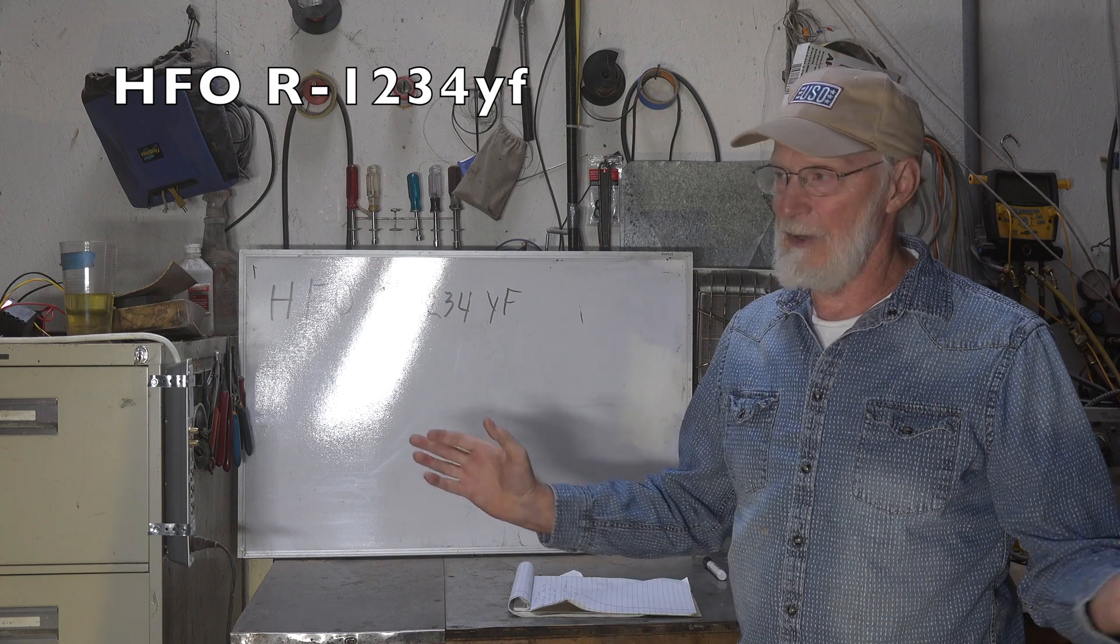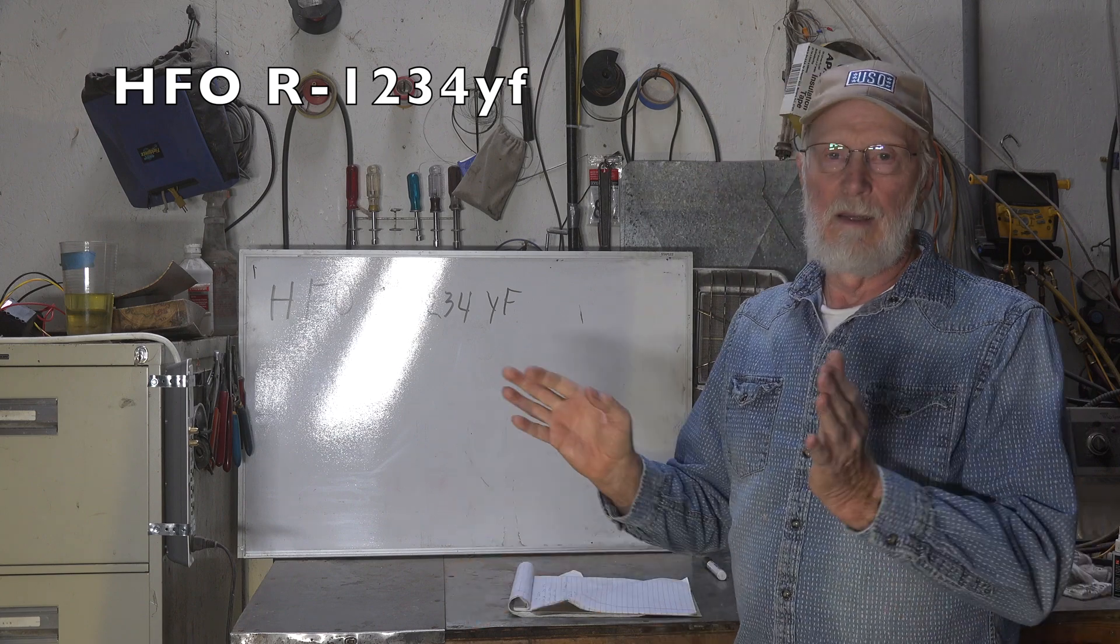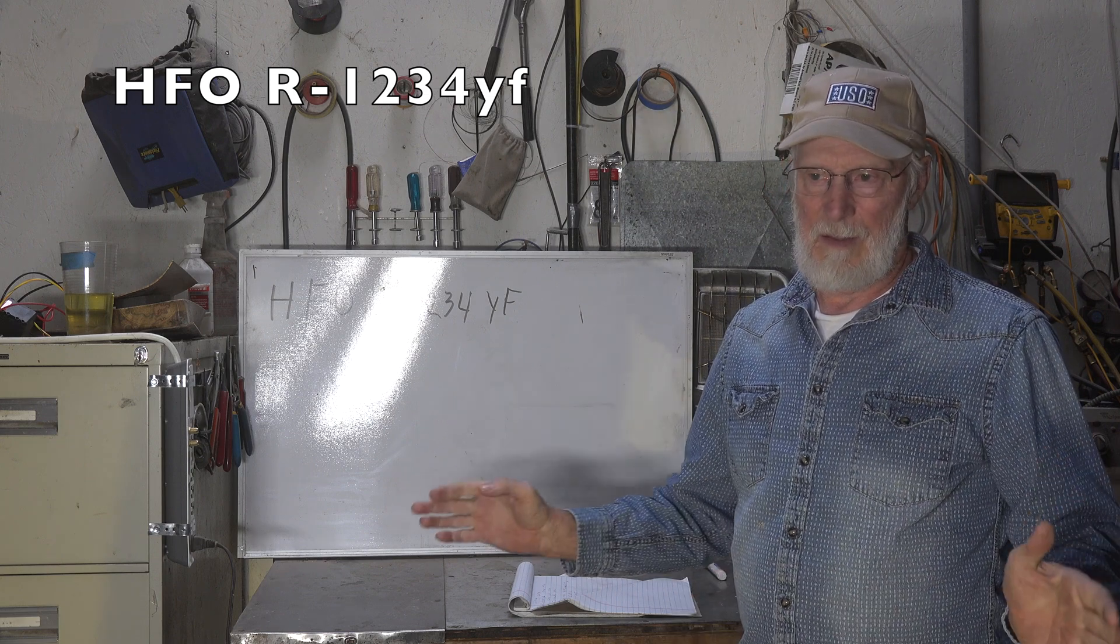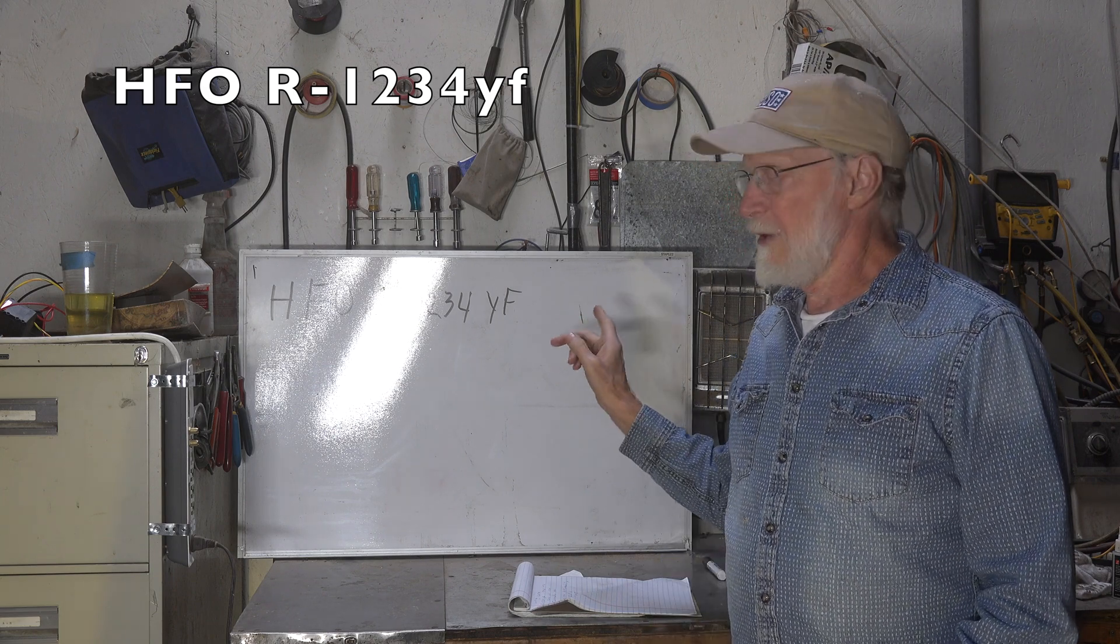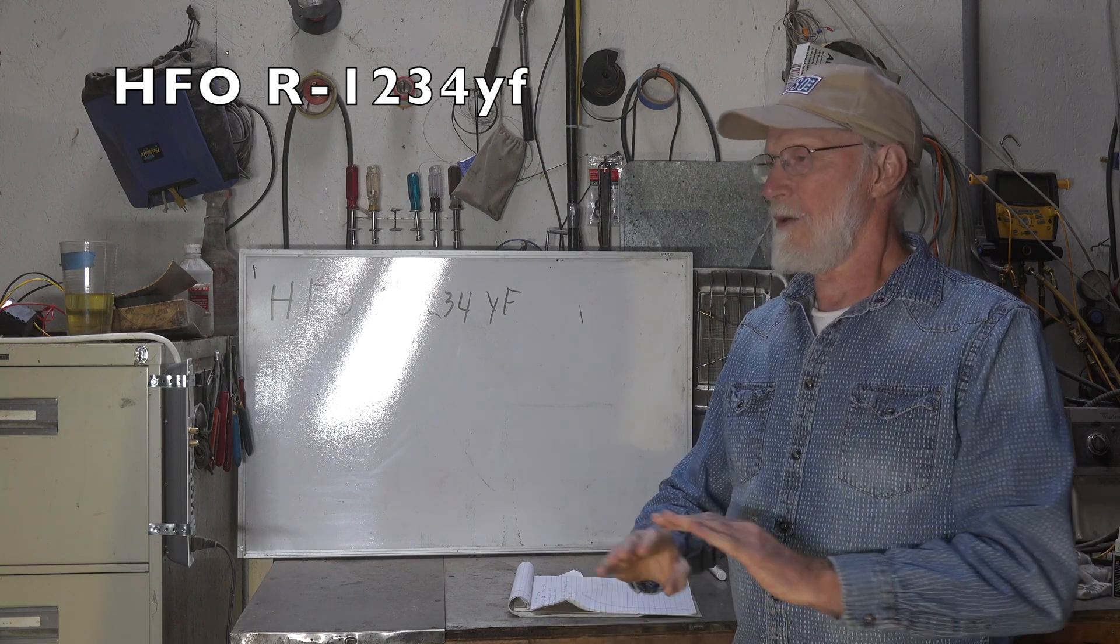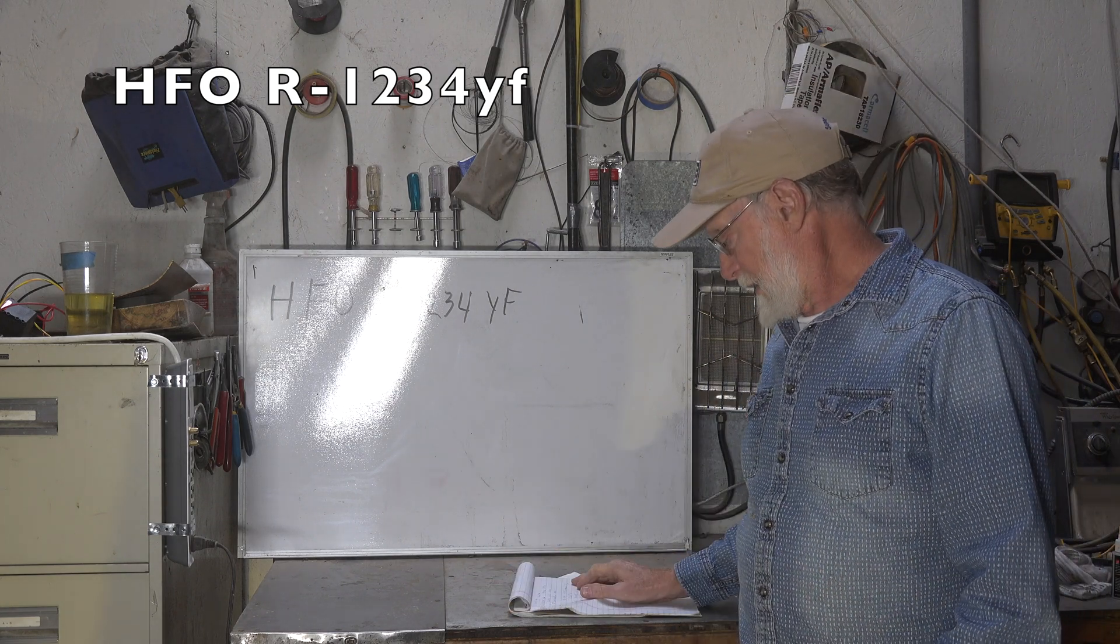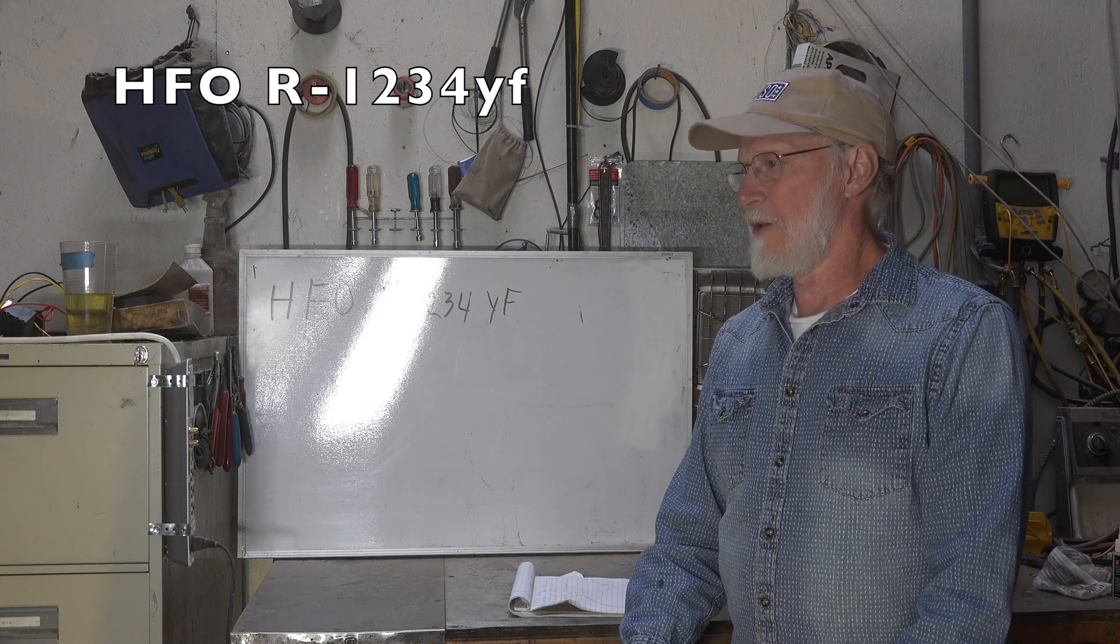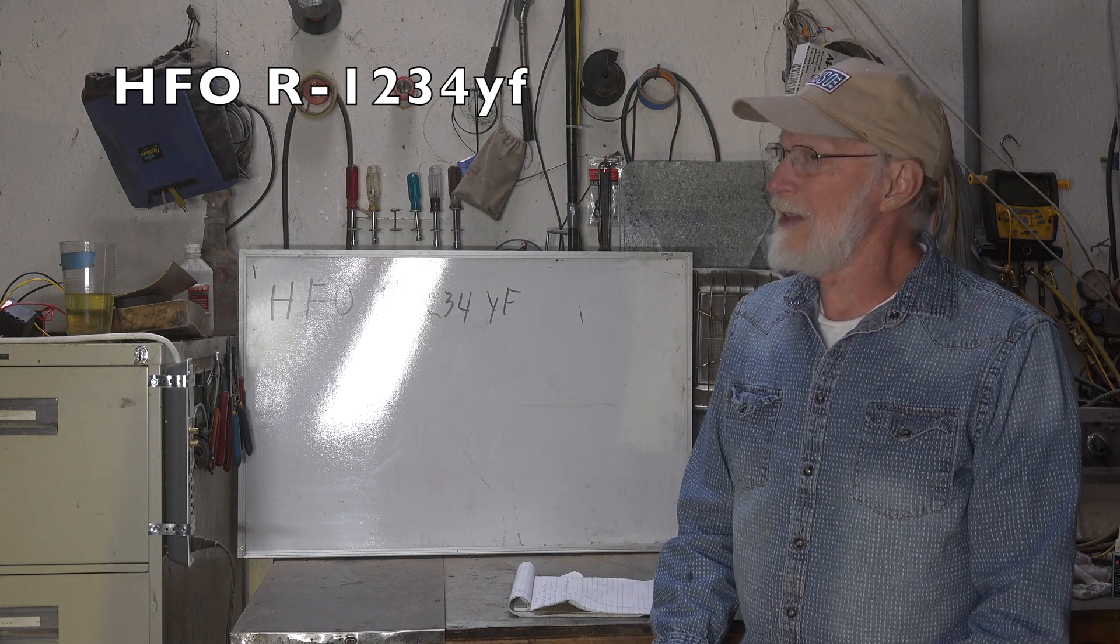Now there's, I think, three ratings of flammability. It's A2. A1 is nothing - that would be R134A. It will not burn. R1234yf will burn. They say it's not as flammable, and there are ways that they can mitigate this. I'm not going to try to go into all that. But it is a flammable refrigerant. If you watch my videos, I've showed you a couple others that say they were A2, and they actually were fairly flammable.